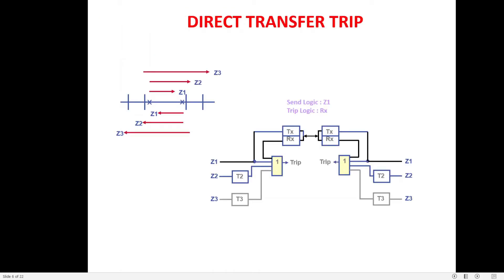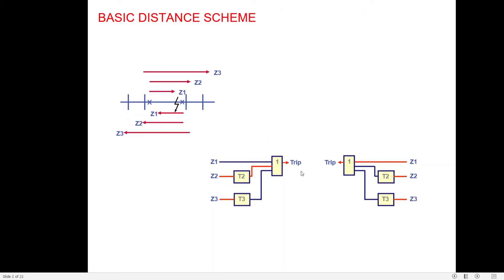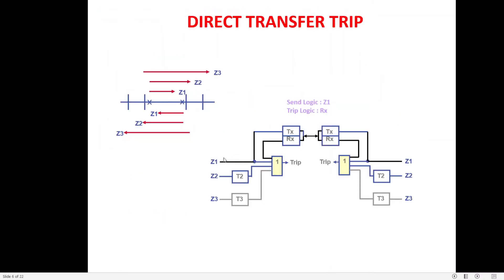The first channel-dependent scheme is Direct Transfer Tripping (DTT). In this scheme, tripping is transferred directly from one end to the other. The end that sees the fault in Zone 1 transfers the tripping signal to the remote end. In the basic scheme, left-hand and right-hand side logics operate separately with no channel connection, but in the DTT scheme they are connected via two PLCC channels.